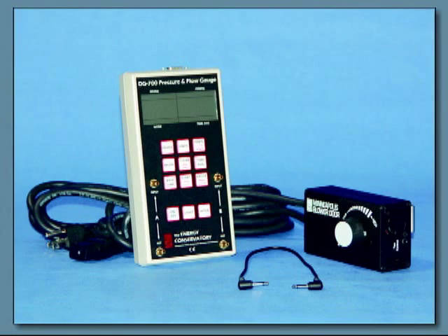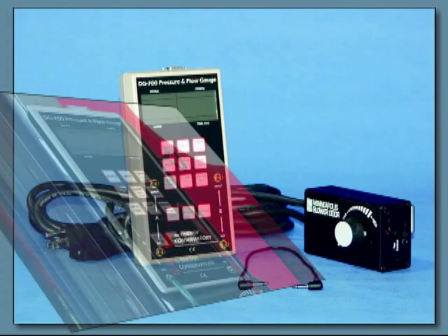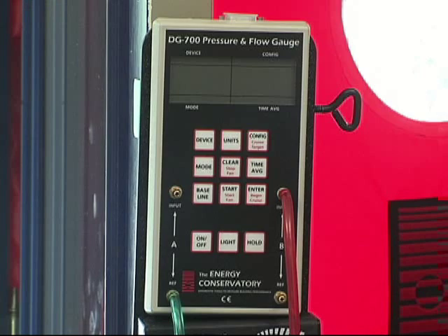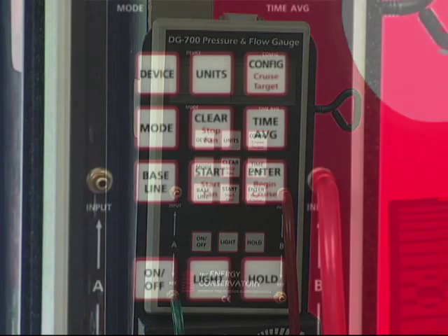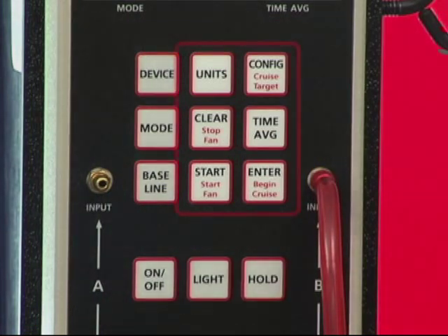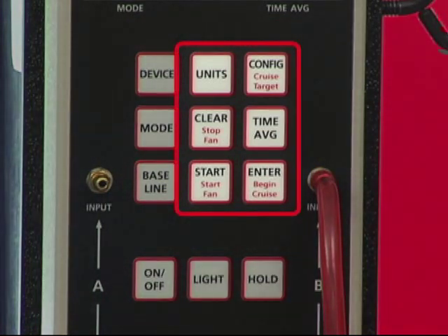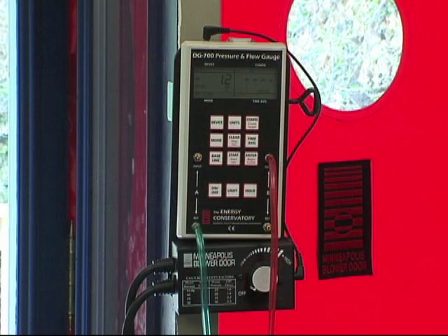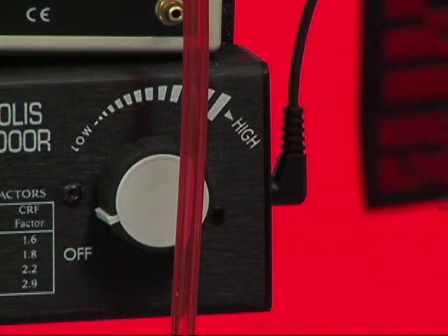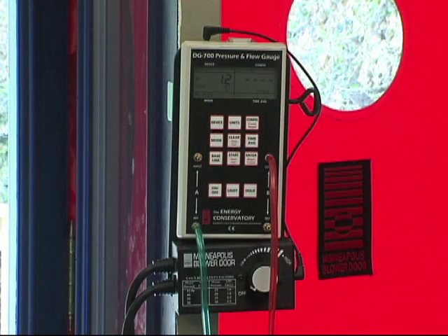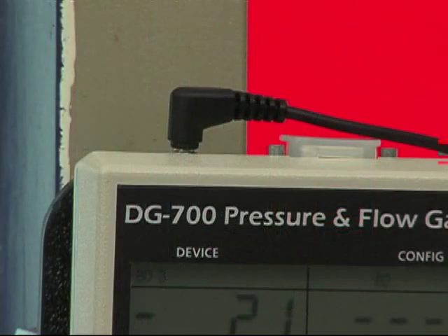In order to use the cruise control feature, you will need the following three items: a cruise-compatible DG700 gauge — your DG700 is compatible with cruise control if the Config, Clear, Start, and Enter keys have additional red lettering below the main black script; a blower door fan speed controller with a 3.5mm communication jack on the side of the controller box, which has been standard equipment since September 2004; and a fan control cable to connect the DG700 fan control jack to the speed controller communication jack.